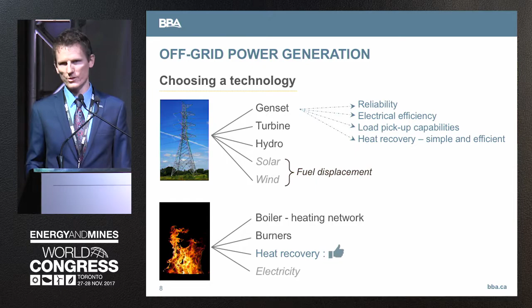We try to avoid decentralized burners, and even more so, electrical heating. That's a no-go, because heating electrically is about half as efficient as heating with a diesel boiler. So that's the technology — we chose the genset.